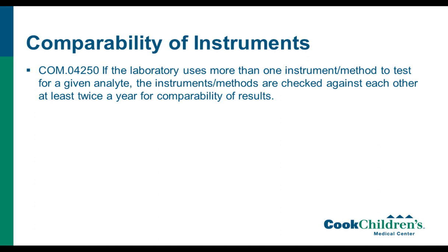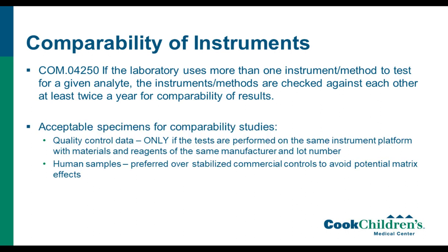In addition to calibration verification and AMR verification, one of the requirements for ongoing quality assurance is what's called comparability of instruments. So if the lab uses more than one instrument or method to test for a given analyte, those have to be compared against each other at least twice a year. So this could be, for example, let's just say CMV Quant. If you have 2 instruments that run it, same manufacturer, same platform, those have to be compared. If for whatever reason you run CMV Quants on 2 instruments by different manufacturers, those have to be compared as well.